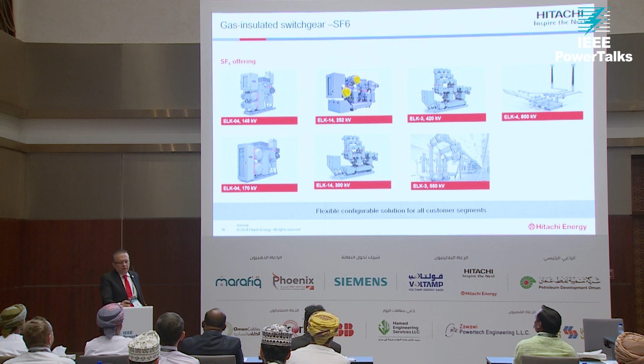But later on, with more study, we found that we and other OEMs are generating a lot of equipment with SF6. Although this gas stays inside the switchgear and we are not releasing it to the air, we know there is some leakage, and per standard, the allowable leak is 0.1% per annum. But the leakage going to the atmosphere is not only that 0.1% per annum.